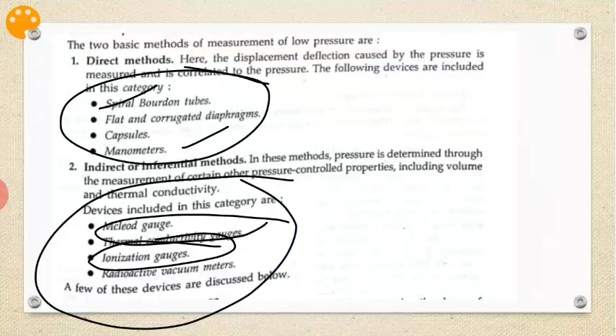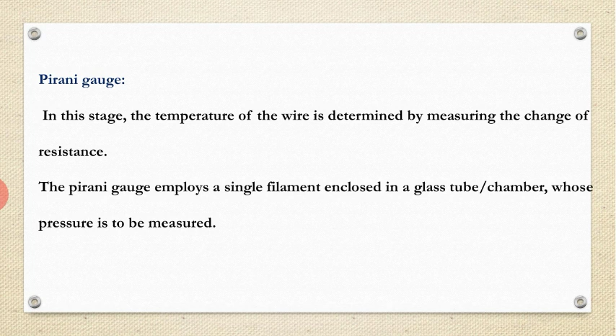The first one is the thermal conductivity gauges, under that the Pirani gauge. What is the Pirani gauge and how does it operate? Now I will discuss. In this gauge, the temperature of the wire is determined by measuring the change of resistance. The Pirani gauge employs a single filament enclosed in a glass tube chamber whose pressure is to be measured.